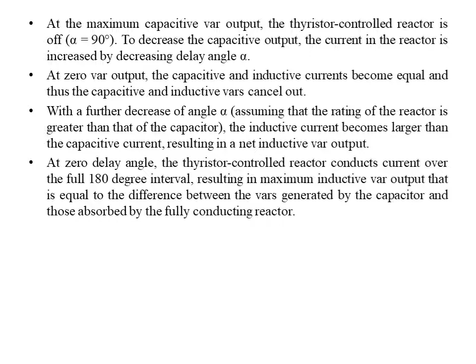So what we have studied till now is that by controlling the firing angle or delay angle of the thyristors, we can have control over VAR generation, from inductive VAR generation or capacitive VAR generation, that is, TCR VAR generation and fixed capacitor VAR generation. This is mainly possible by just controlling the firing angle or delay angle alpha of the back to back connected thyristors. Now next, how we can control the back to back connected thyristors, that is, control of the thyristor controlled reactor in FC-TCR. So how we can produce the gate pulses will be studied at this point.